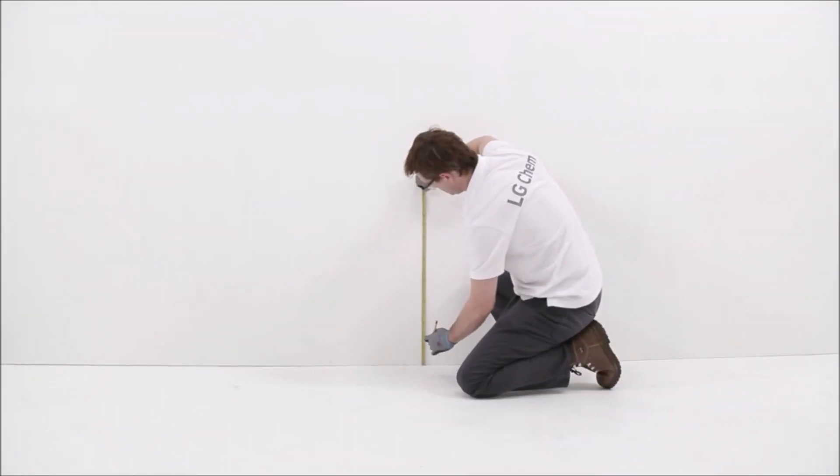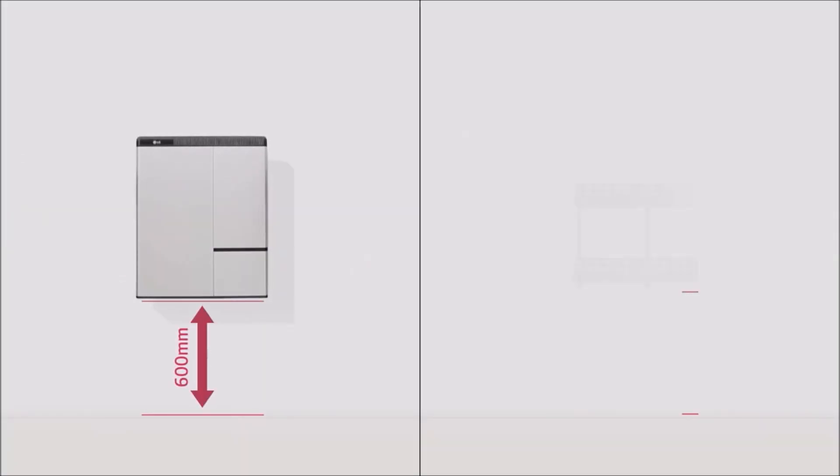First, the wall mounting bracket needs to be fixed. Please note that the RESU 7H and RESU 10H can only be wall mounted. For wall mounting bracket installation, make sure you have at least 720 millimeters above the ground.